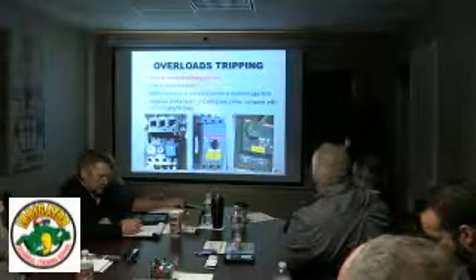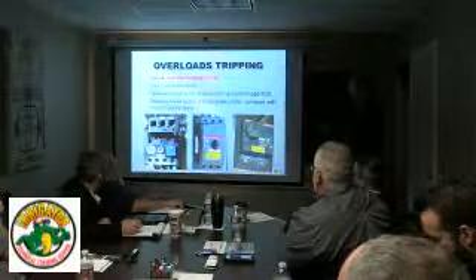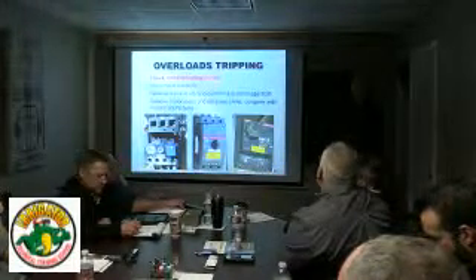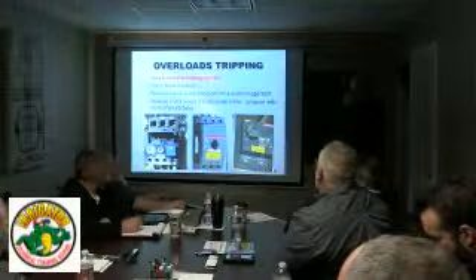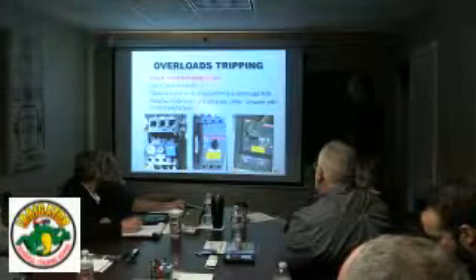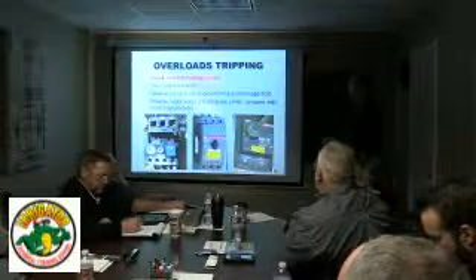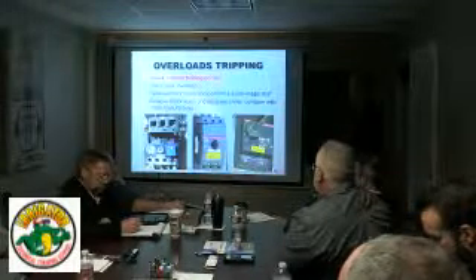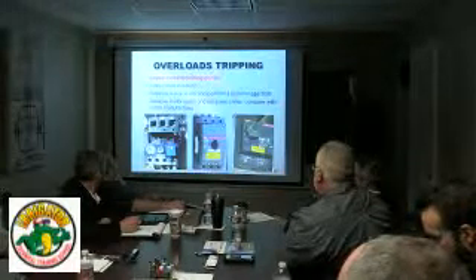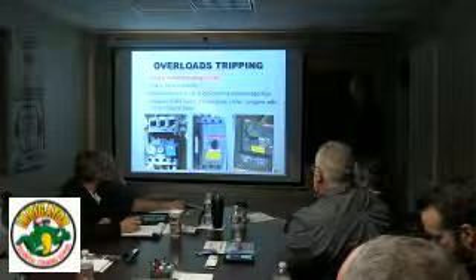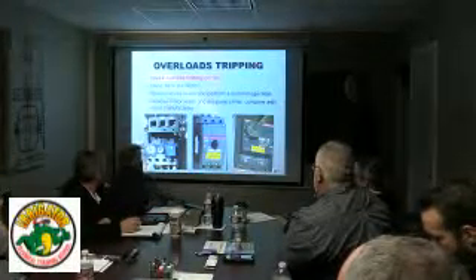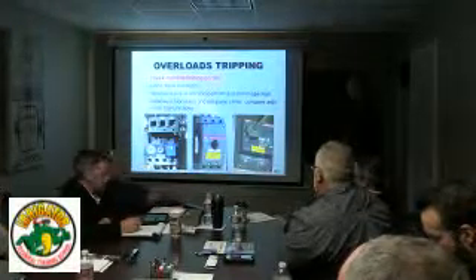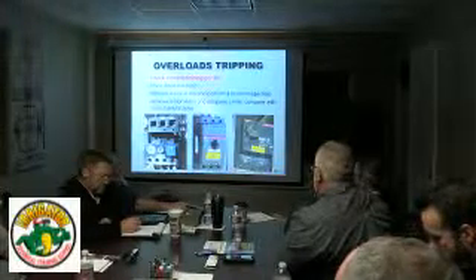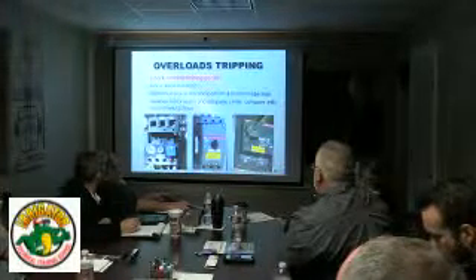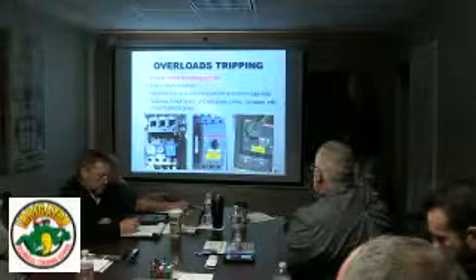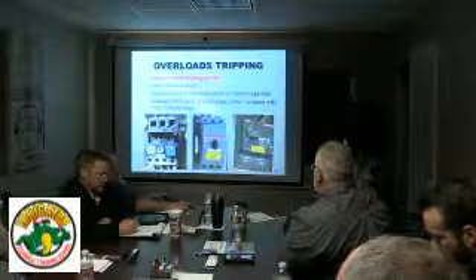All you have to do is push the blue button. A lot of times if you push the blue button and it clicks, that means it's been tripped. So if you have an overload that keeps tripping, double check your amp rating right here. You can dial that. That's the setting for that overload when it's gonna trip. Might be one thing that you'll check. Another time when that clamp on amp meter might come in handy, check these 3 leads going out. These will trip if a couple of them are normal and one of them's way over.